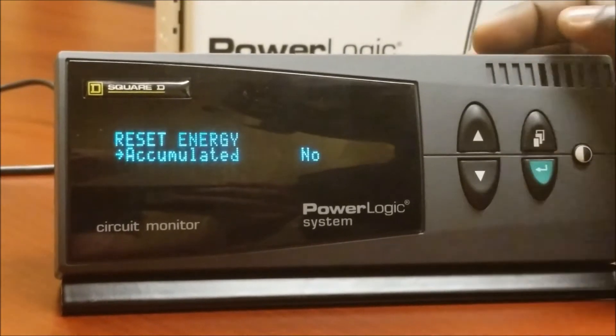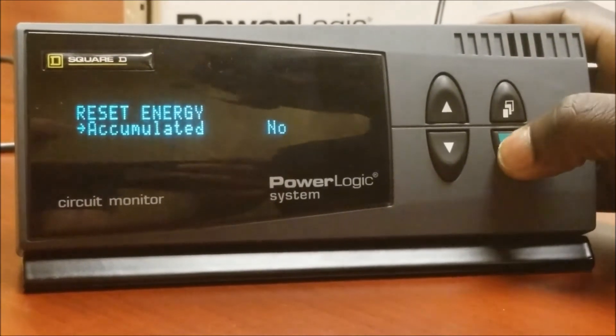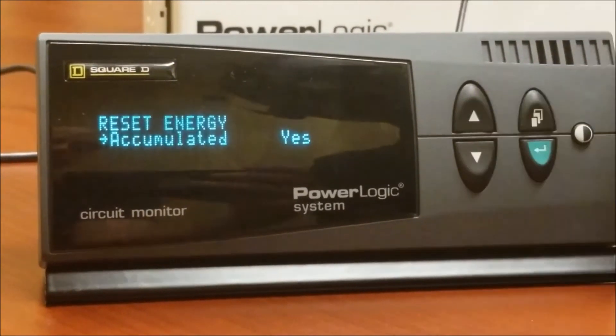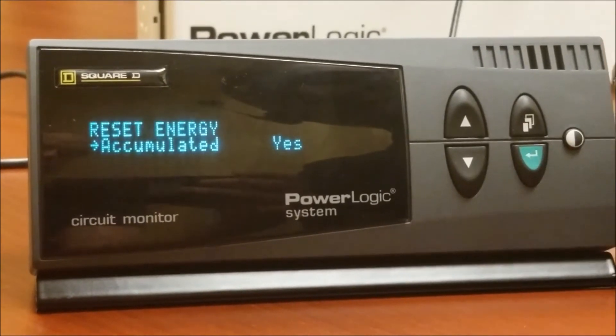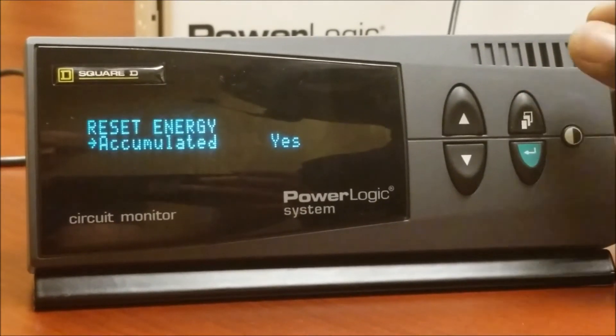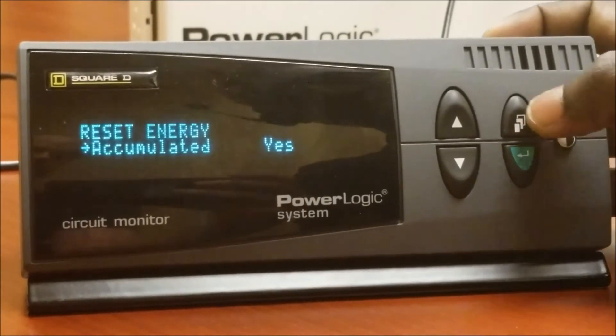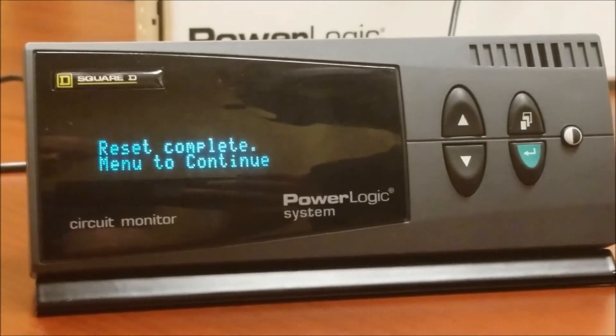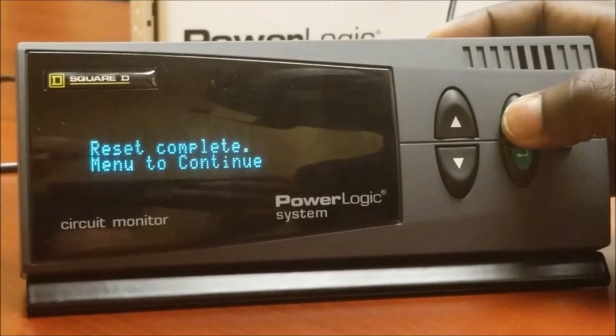It's going to ask us if we want to reset the accumulated energy. Press the enter button — the no will start flashing. Press the up arrow to switch it to yes, then press enter one more time. It's going to become a steady yes with no more flashing.